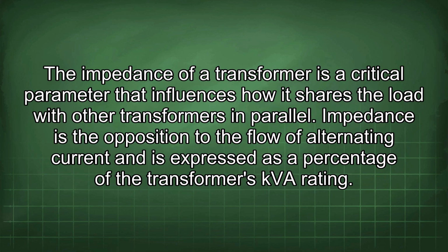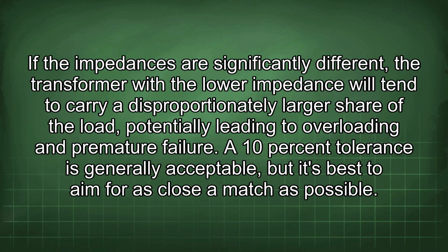The impedance of a transformer is a critical parameter that influences how it shares the load with other transformers in parallel. Impedance is the opposition to the flow of alternating current and is expressed as a percentage of the transformer's kVA rating. If the impedances are significantly different, the transformer with the lower impedance will tend to carry a disproportionately larger share of the load, potentially leading to overloading and premature failure. A 10% tolerance is generally acceptable, but it's best to aim for as close a match as possible.